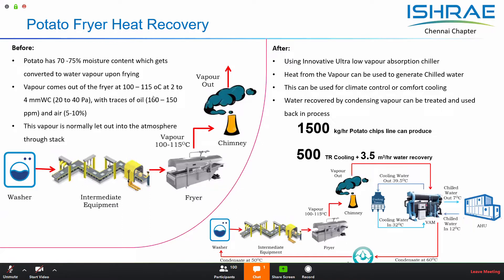Conventionally, these vapors are let out into the atmosphere, which causes two losses: first, you are releasing heat at a high temperature unrecovered; second, what is going out is nearly pure water vapor. By introducing an absorption chiller in between, the vapor from the fryer can be taken into an absorption unit where it will be condensed inside the generator, and that heat can be recovered to produce cooling. The snack industry also requires air conditioning to maintain temperature and humidity in the packaging unit to ensure the crispness of the chips is not lost.